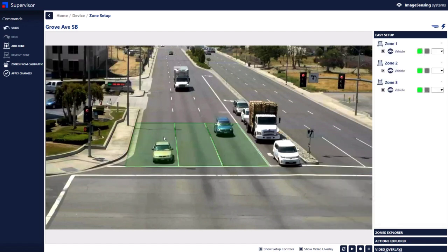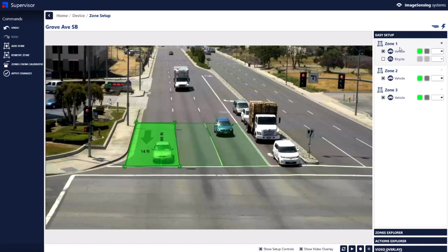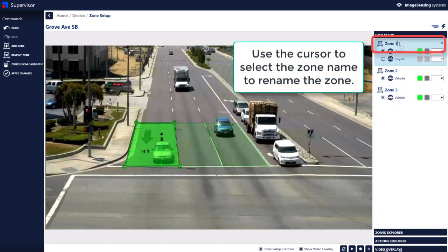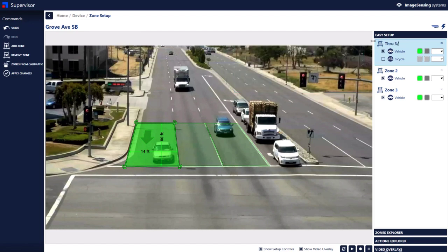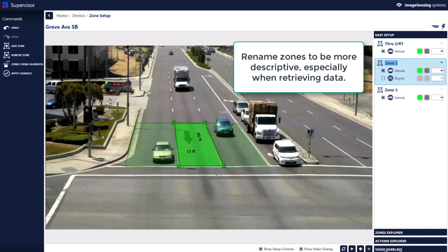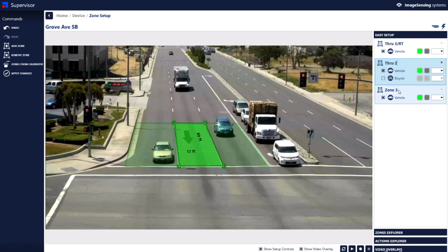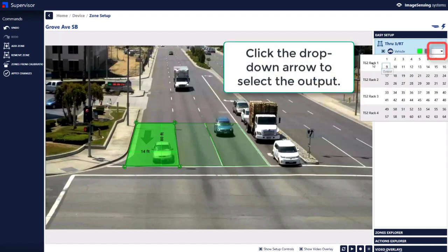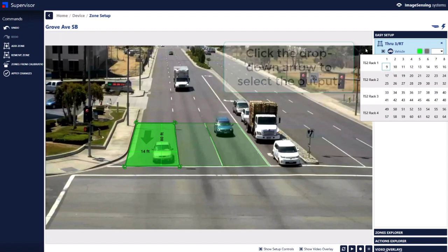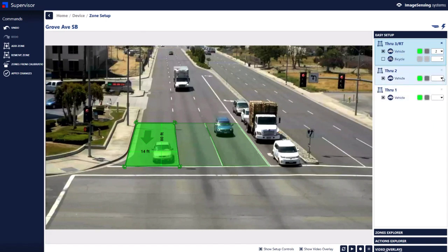These are the ones that were used in calibration. If I click here you'll notice it highlights over on the right side. I can click, drag over, and put a name here. It's always good to name zones so that they are useful when you're retrieving data and referring to them in various places in the system. The IO drop-down list gives me my TS2 racks 1 through 4. If there's an IO24 module connected, I will see the 24 outputs from TS1 as well. We're going to set these all to output 2.